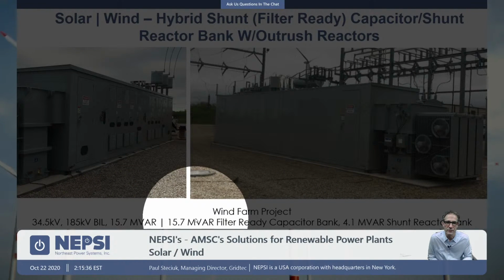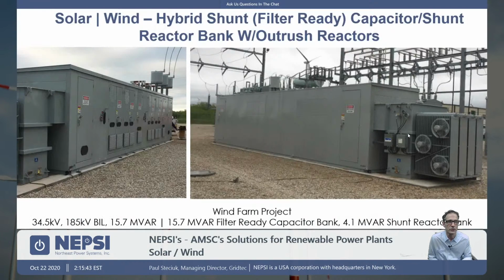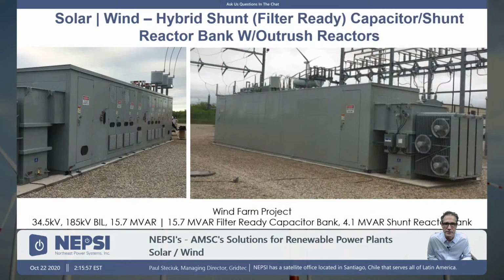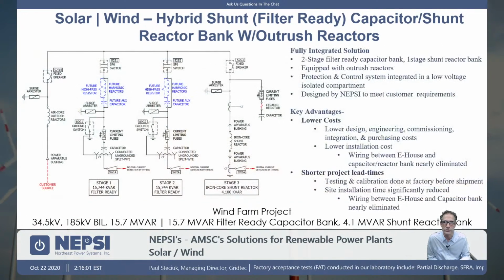So this is a 2-stage 15.7 and 15.7 Mvar for capacitors, and it's got this shunt reactor 4.1, and we're going to be talking about that, and that's here. It's a shunt reactor, and it's an iron core reactor immersed in oil, so it's very compact. Again, a very compact solution for this customer. And we have outrush reactors here. We have a tech talk where we talk about the requirement for outrush reactors. Maybe 3 or 4 tech talks ago, we talked about that requirement for outrush reactors. Here's the one-line diagram for this system.